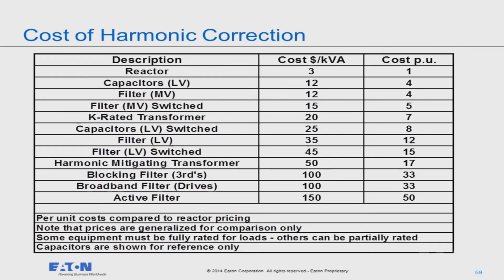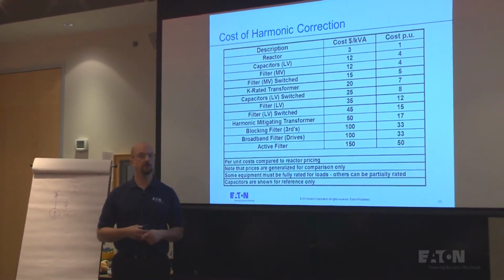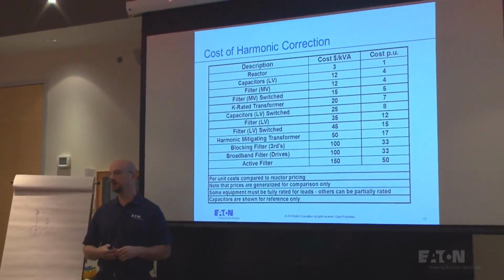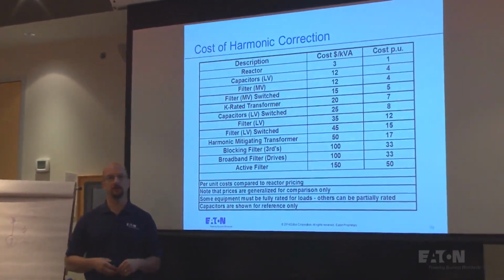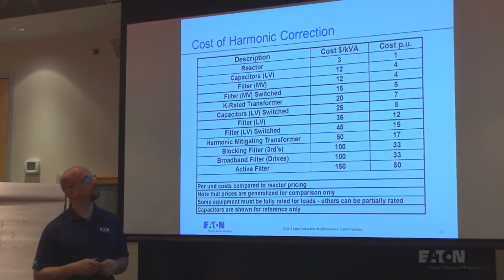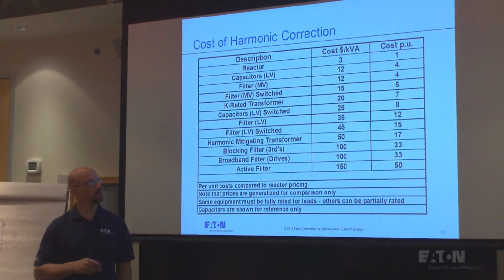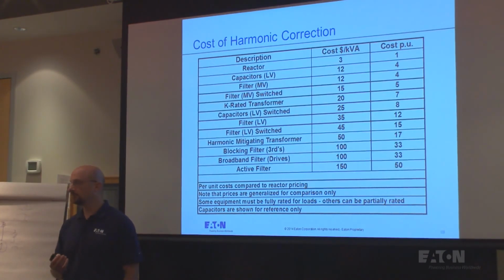This is just a simple cost comparison. If I were to do nothing but put line reactors in there, I've actually done it at a pretty low cost, right? But if you put in a drive that doesn't have AC or DC reactors, you're going to have a lot more harmonic current, and it doesn't really cost that much to add that reactor into the drive and get that benefit. So this is a really key point here: this is a very inexpensive way to get the harmonics to a reasonable level. At that point, then you deal with them another way.